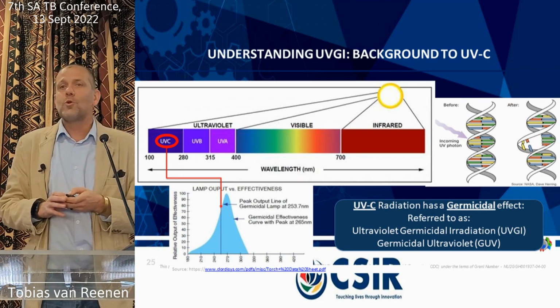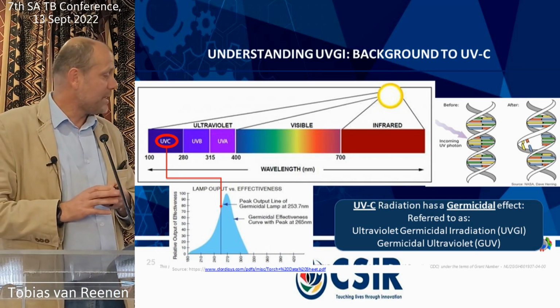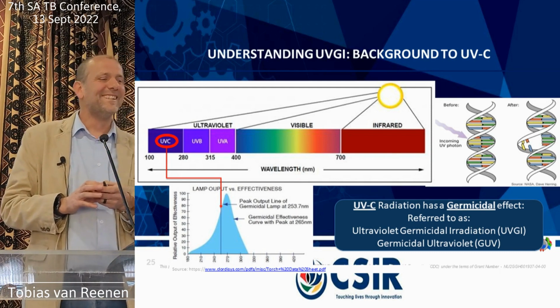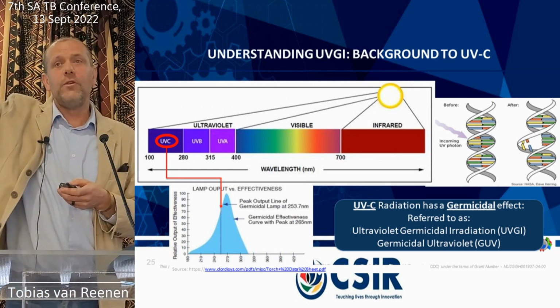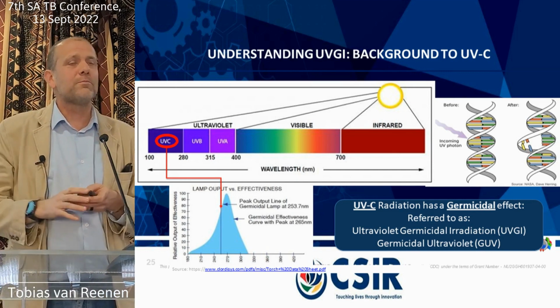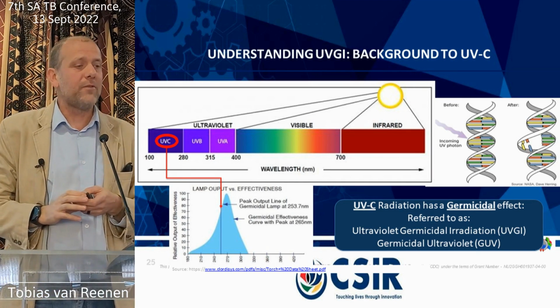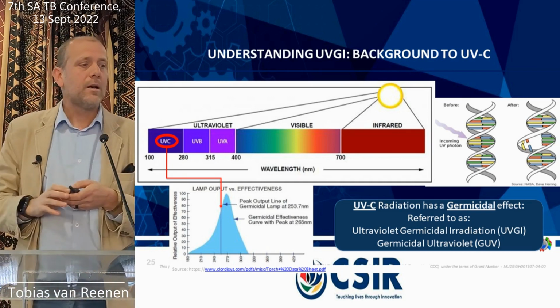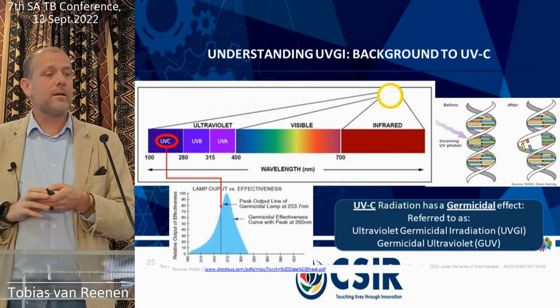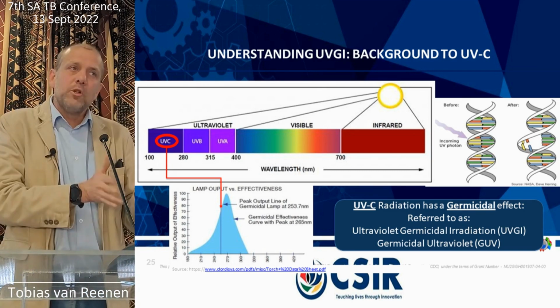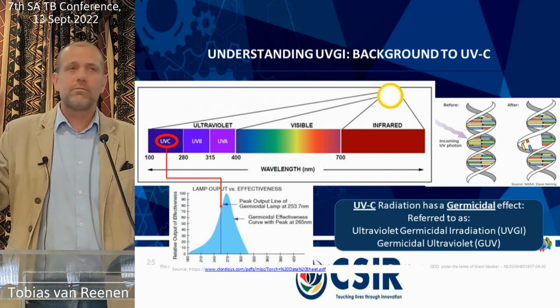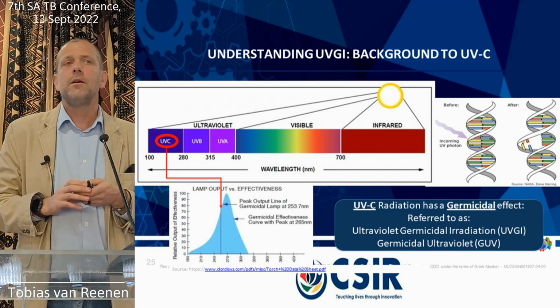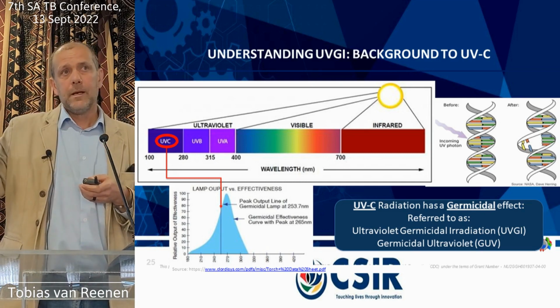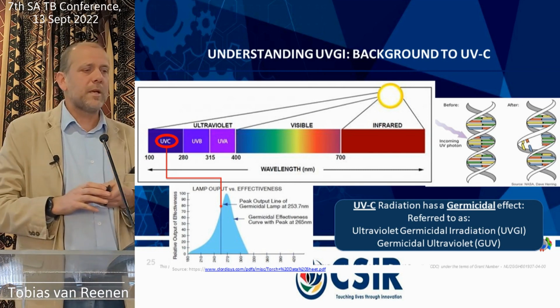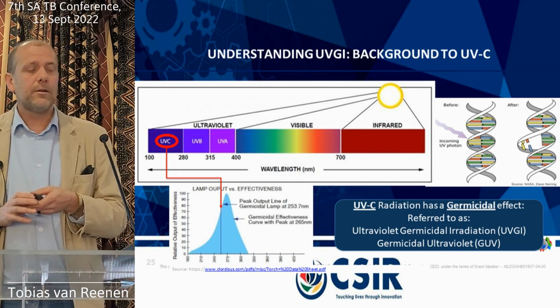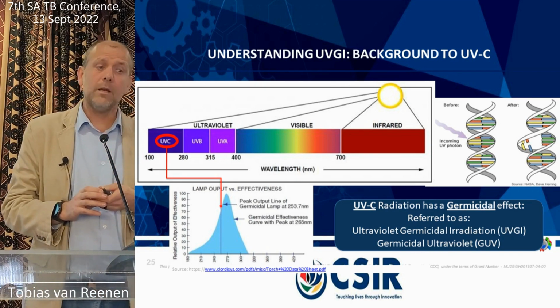You must have all heard a UVGI talk by now, so I'm going to rush through this, and I think I'm just about out of time anyway. No, keep going. Okay. All right, so UV is a spectrum within the electromagnetic wavelength, a little subspectrum. You can see it over there. UVC is between 100 and 280 nanometers. When we speak about UV today, we still largely talk about 254 nanometers, and that's just what the cheapest lamps give us. The emerging technology is 222 nanometer, and some of the UV LEDs, which I think are still quite expensive, can tune those wavelengths to give us greater efficiencies at quite a cost.